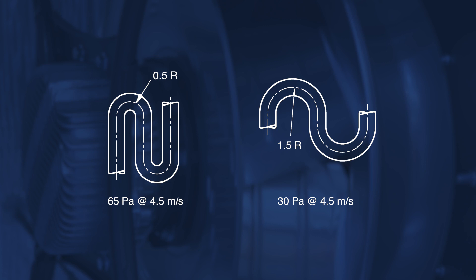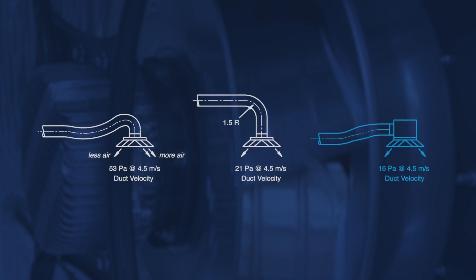Avoid S-bends, as these can generate more than double the pressure loss of a 180 degree bend — in fact, about 2.5 times the pressure loss. Side entry diffuser boxes generally have a much lower pressure loss than top entry diffuser boxes.